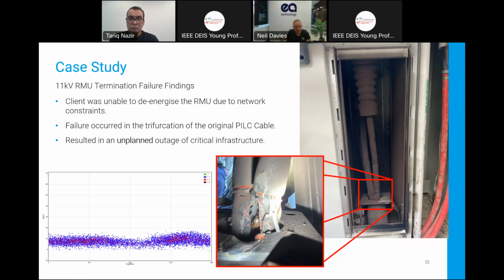So there's a lot of things you can interpret from the PRPD plot. You can interpret, is it corona? Is it internal void? Is it surface type discharge? Is it contact discharge? How many phases are involved? All of these things can be interpreted through experience, as long as you make sure you're grabbing the phase reference and referencing all the measurements you're taking to a local 50 hertz reference.